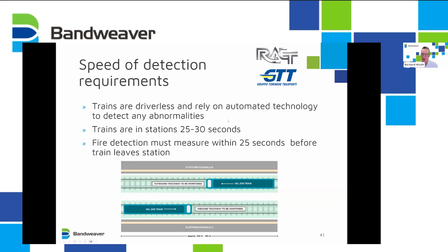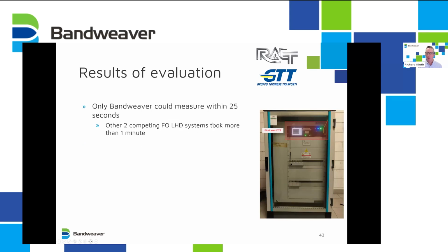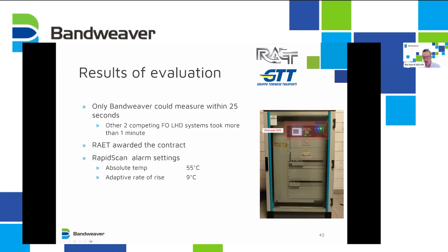Because the trains were driverless and relied on automated technology, they need to detect abnormalities. There isn't a driver to make a decision and say, I can see signs of a fire, and not proceed in there or raise the alarm. So the trains are in station 25 to 30 seconds. So the fire must be measured within the 25 seconds before the train leaves the station. Only Bandweaver was able to do it within 25 seconds. The other competing systems took more than a minute. RAET were awarded the contract.